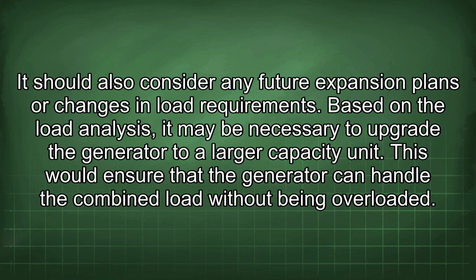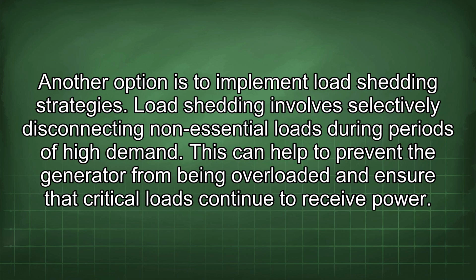Based on the load analysis, it may be necessary to upgrade the generator to a larger capacity unit. This would ensure that the generator can handle the combined load without being overloaded. Another option is to implement load shedding strategies. Load shedding involves selectively disconnecting non-essential loads during periods of high demand. This can help to prevent the generator from being overloaded and ensure that critical loads continue to receive power.